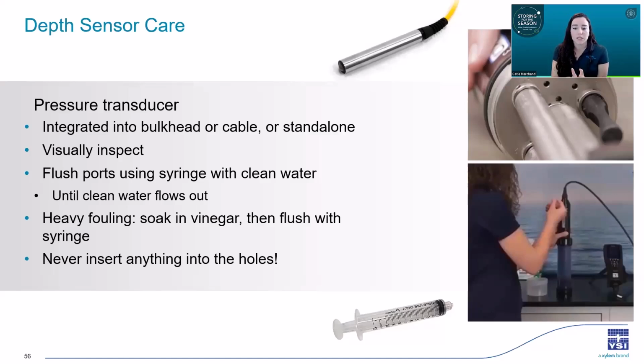And if you're noticing that something's stuck in the holes, if you're looking in there and you can see something, you can soak it in vinegar. To do that, you can just take your instrument, put a little bit of vinegar in your calibration or your storage cup, and tighten it on the instrument, because you don't want to dump vinegar everywhere. Then you're going to invert the instrument so that vinegar enters the ports, let it sit for 15 minutes, and then flush the ports again with clean water. And if you do see something trapped in there, never insert anything in the holes to get it out. It can damage the pressure transducer and it would need to be repaired by the factory.